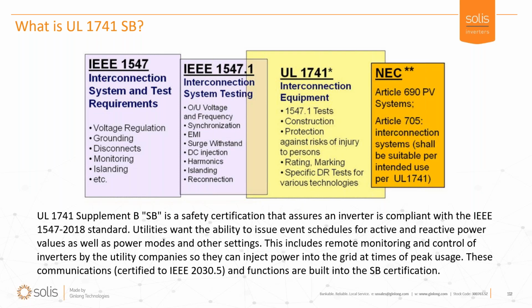They want surge to not kick off all the inverters right away. In the old days, they called it anti-island, where the inverter, as soon as it felt any wobble in the grid, boom, it would click off. And the utility companies found that kind of performance really isn't ideal.